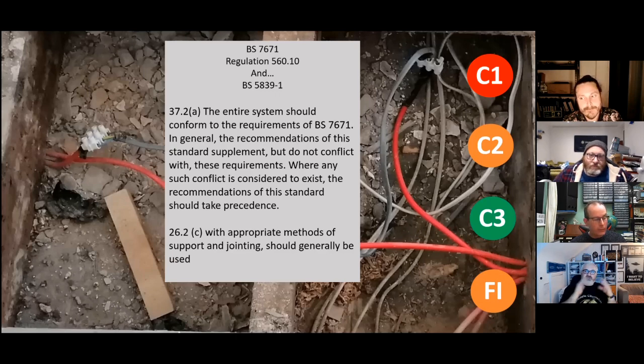So if you say to someone, oh, the fire alarm, I want to code it like this, and someone goes, oh, don't be stupid. No, you're not being stupid. Adding to this, this is likely to be an electrician doing work, so let's say in the future, an electrician may find this when doing work. A fire engineer or maintainer doing maintenance won't discover this in routine testing, will they? Right. How could they? Very likely that they wouldn't.